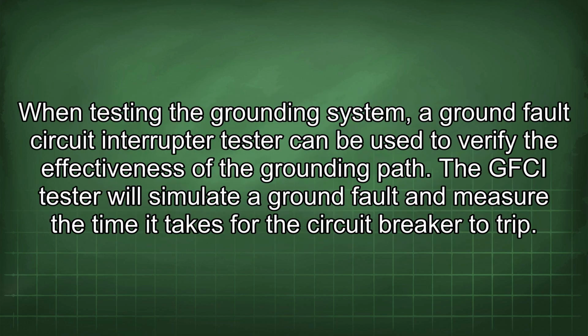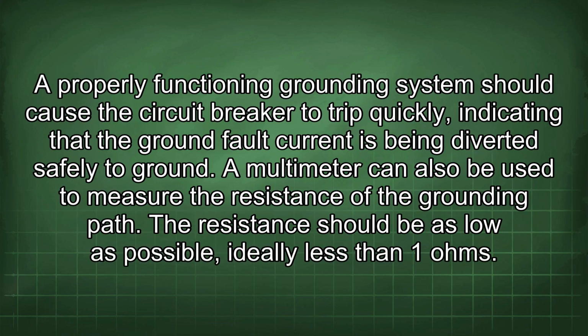When testing the grounding system, a ground fault circuit interrupter tester can be used to verify the effectiveness of the grounding path. The GFCI tester will simulate a ground fault and measure the time it takes for the circuit breaker to trip. A properly functioning grounding system should cause the circuit breaker to trip quickly, indicating that the ground fault current is being diverted safely to ground.